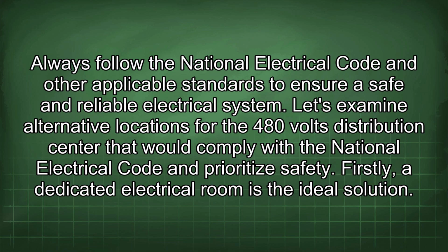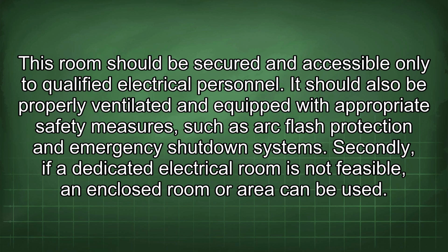Let's examine alternative locations for the 480 volts distribution center that would comply with the National Electrical Code and prioritize safety. Firstly, a dedicated electrical room is the ideal solution. This room should be secured and accessible only to qualified electrical personnel. It should also be properly ventilated and equipped with appropriate safety measures, such as arc flash protection and emergency shutdown systems.